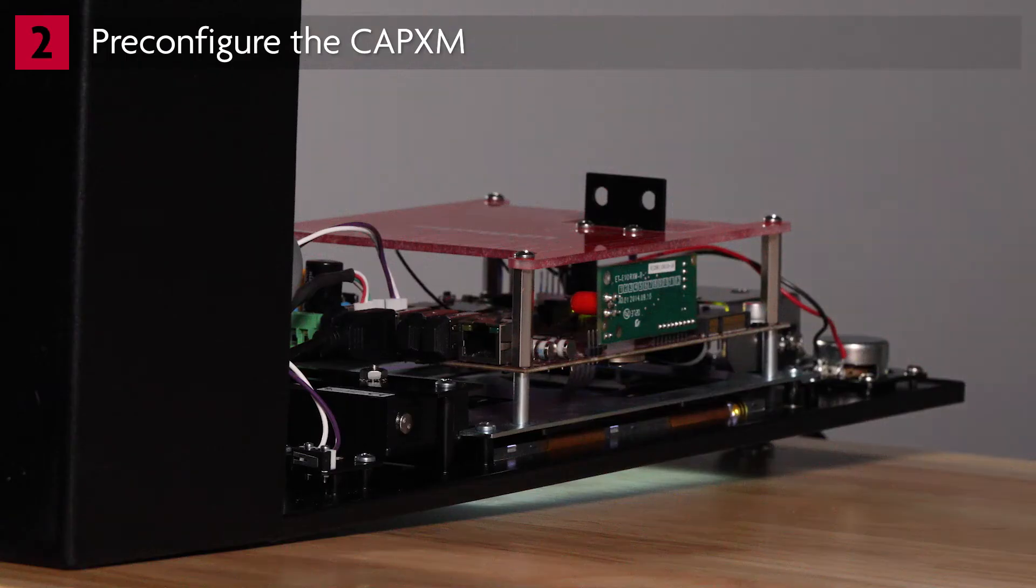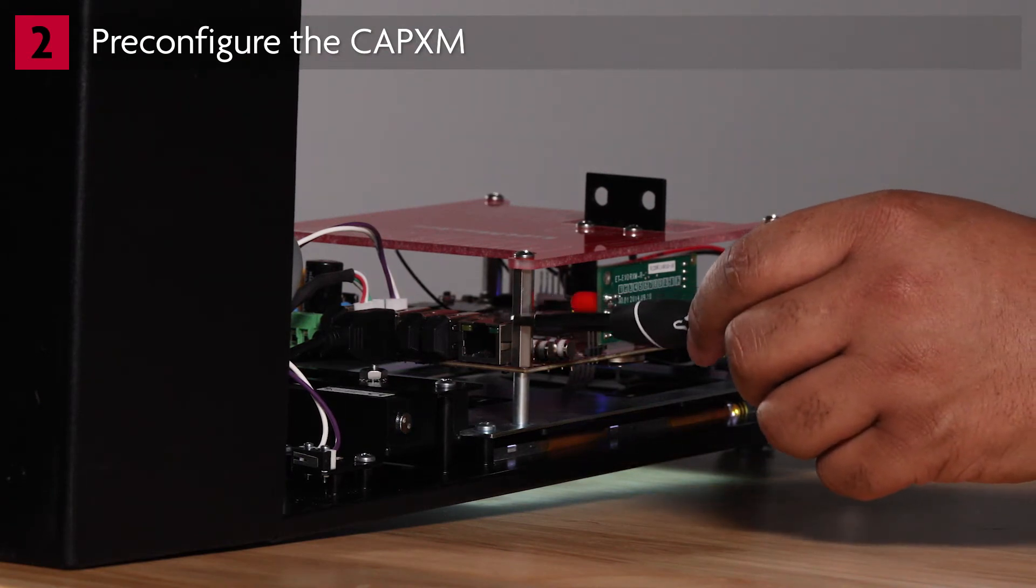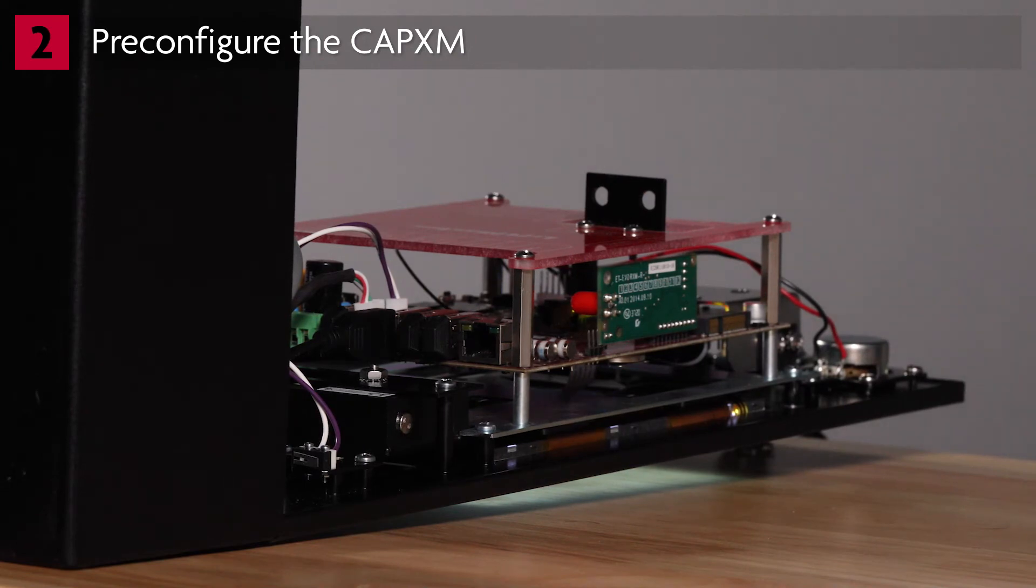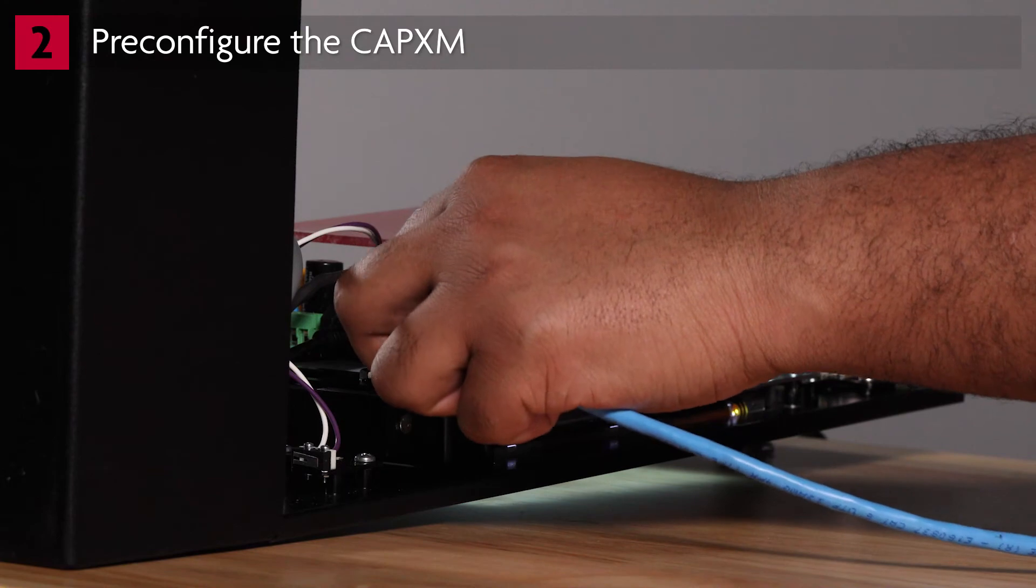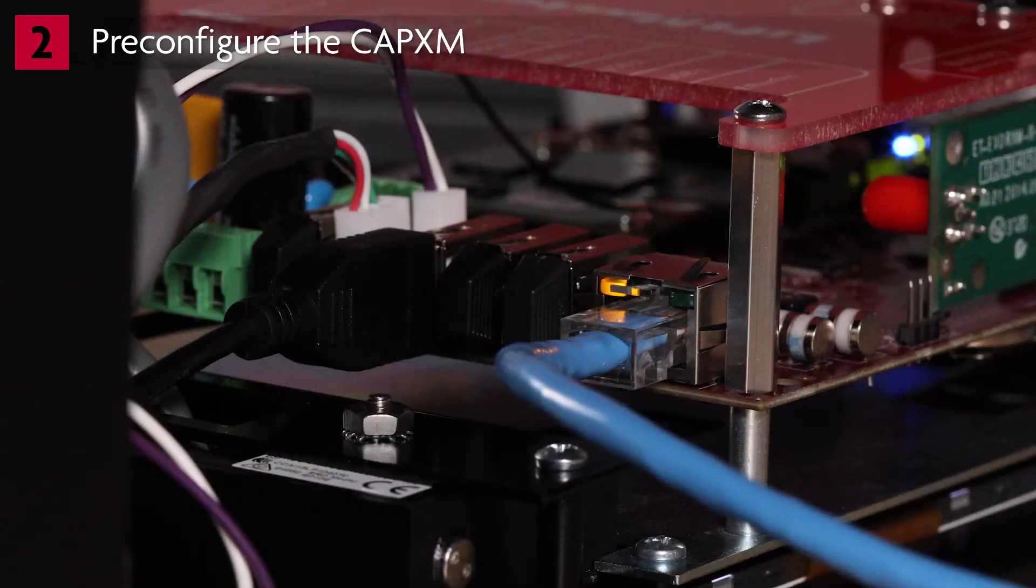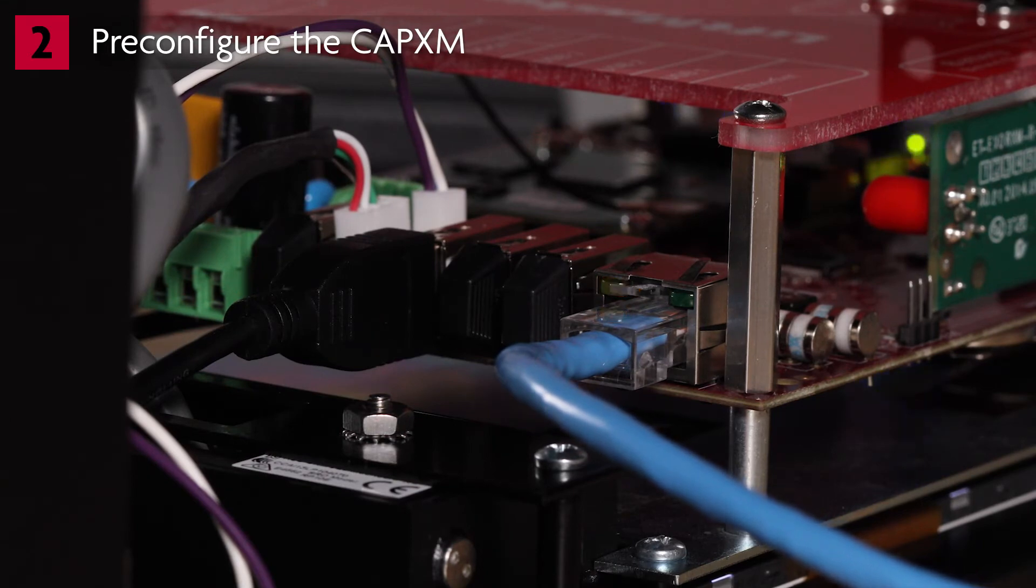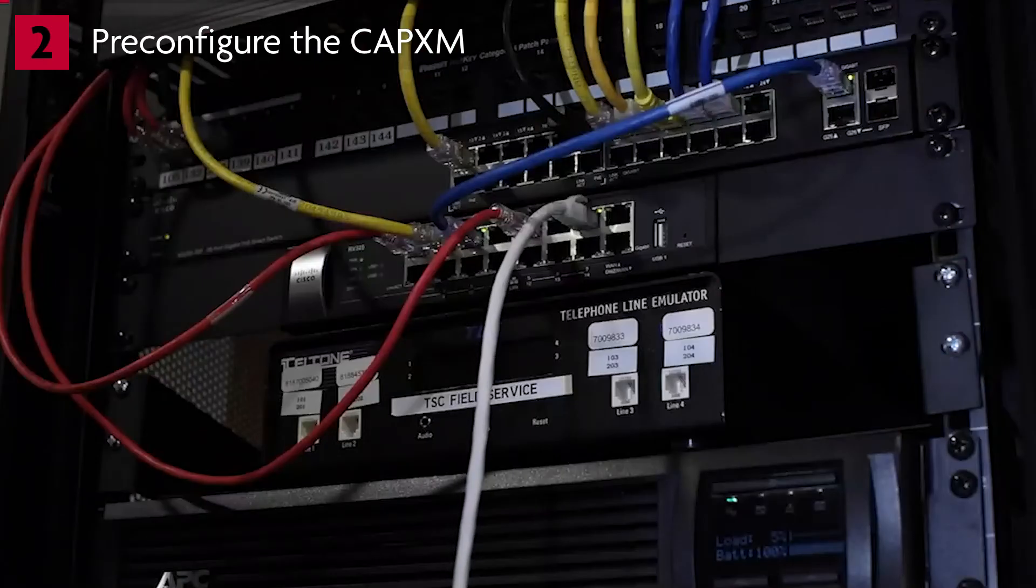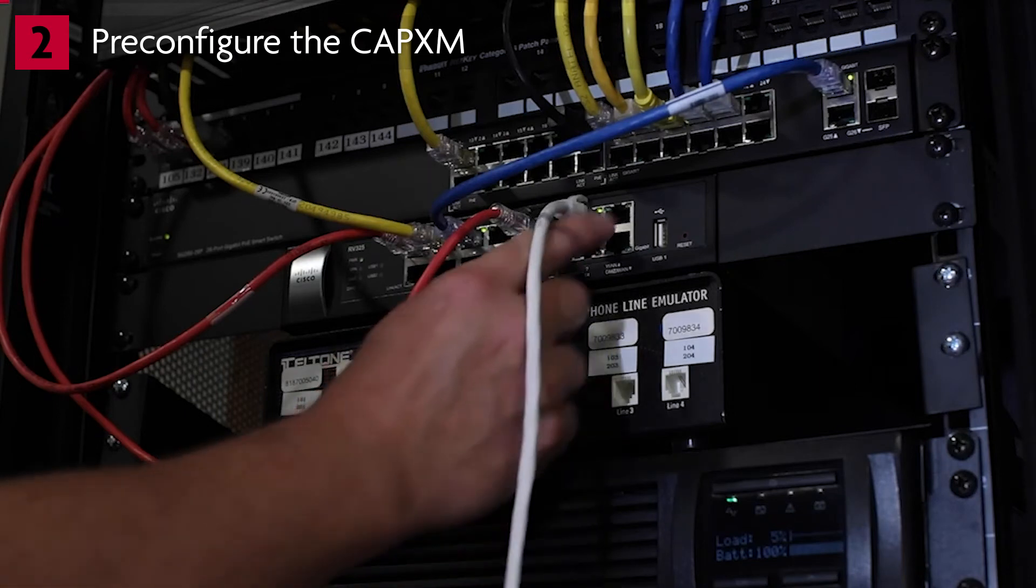For this demonstration, we'll be connecting to a wired network. Locate the LAN port on the control board and the LEDs on the LAN port. Connect the Ethernet cable from a hub, switch, or router to the LAN port on the control board. When a connection to an active network device is established, the yellow LED on the LAN port will light up or flicker. If the yellow LED is not lit, first check that the router is powered up. Also, check the connections on the CAPXM and the router.